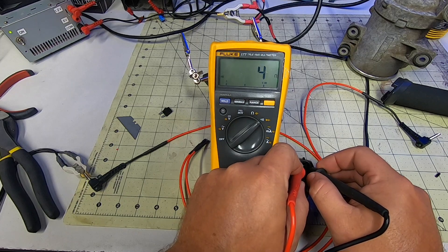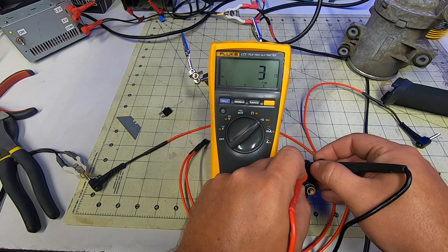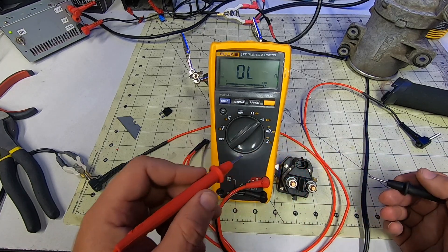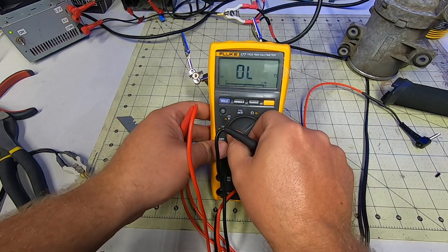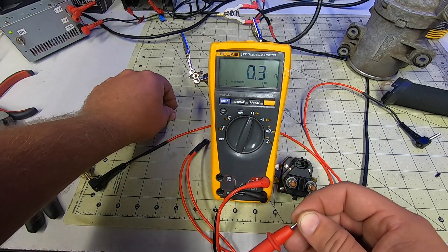The problem comes when you de-energize this coil. What you'd see if you had much more sophisticated equipment than I have here is a reverse polarity spike or discharge of that coil many times the input voltage. This dissipation will significantly shorten the lifespan of traditional toggle or key switches, as well as potentially wreak havoc on all the expensive electronics upstream in my panel.